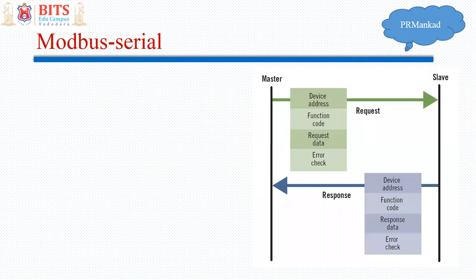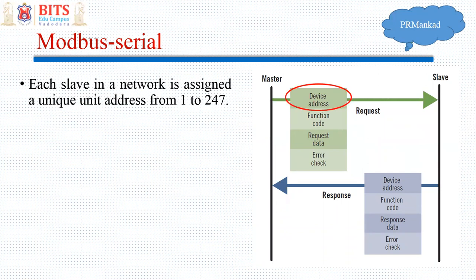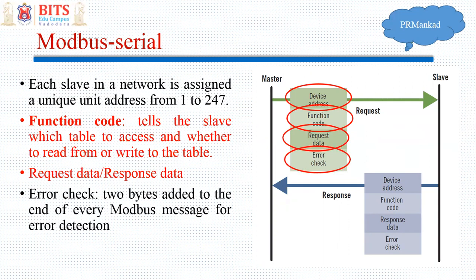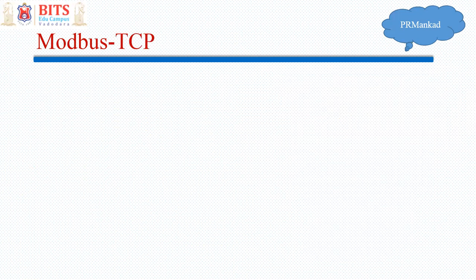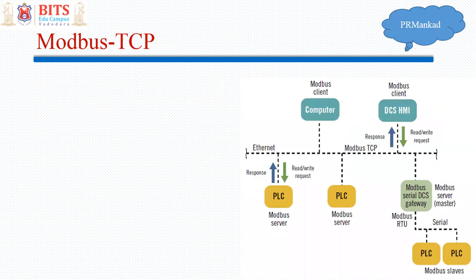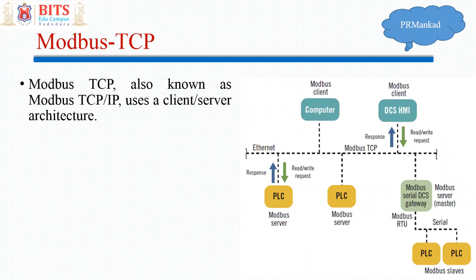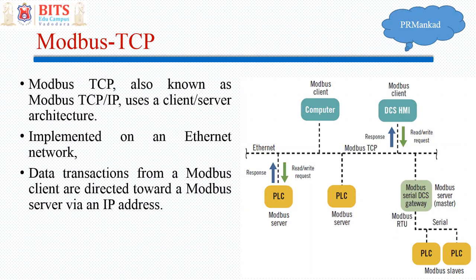In Modbus Serial, the master and slave communicate in a request-response fashion. The frame consists of device address, function code, request data or response data. Modbus TCP is generally Ethernet-based, using a client-server type of communication. Modbus TCP/IP uses a client-server architecture and works on an Ethernet network.